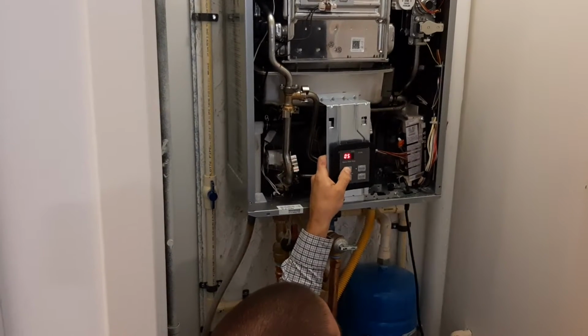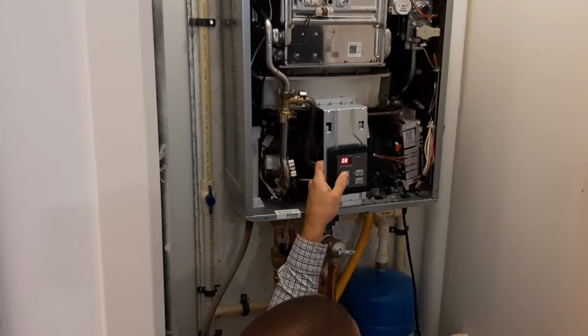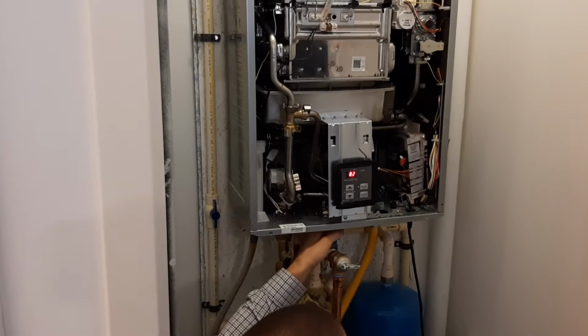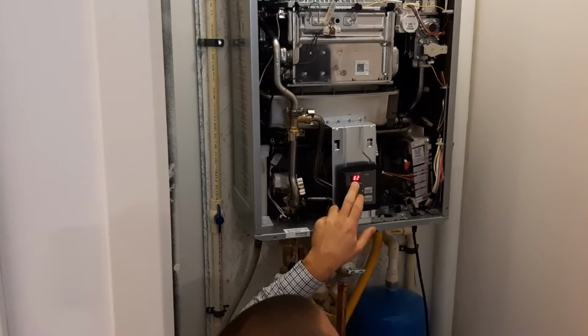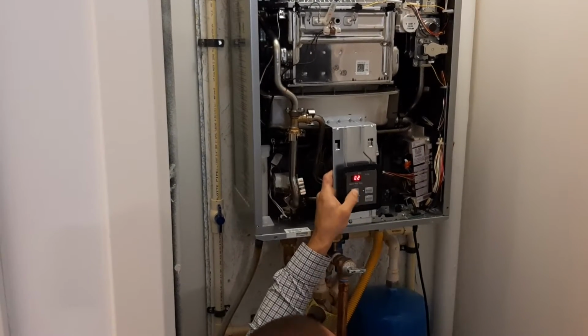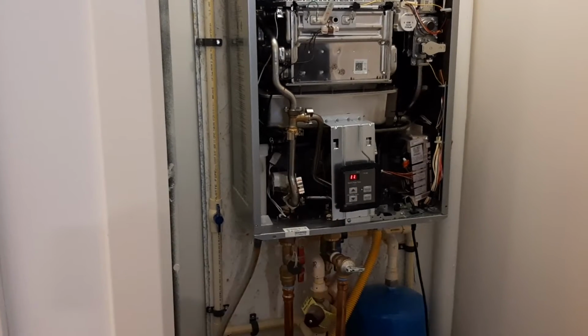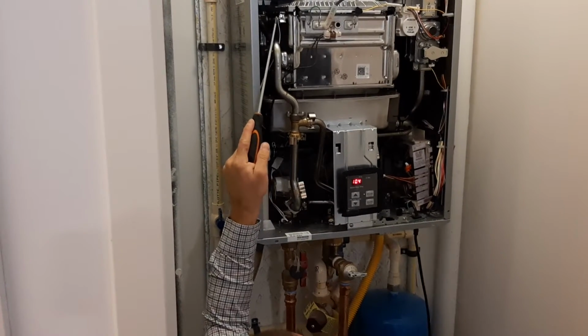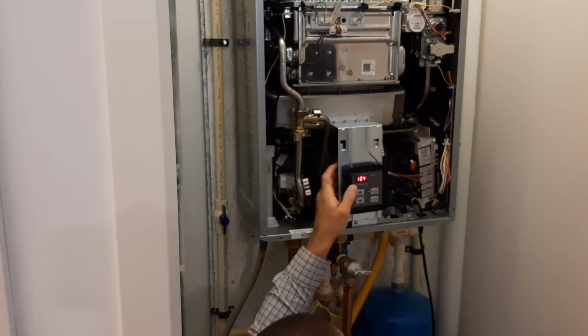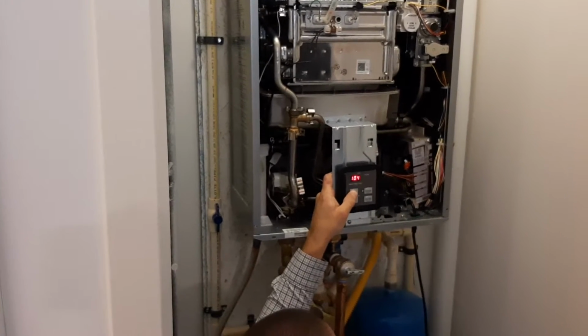Something else good to know is number 8 and 11. Number 8 is my incoming water temperature, so what's coming into the unit. Since we're not running, it's similar to the outgoing. Number 11 is my heat exchanger temperature, read from this sensor. The heat exchanger is a little warmer just because it hasn't cooled off as fast as water sitting in the piping.